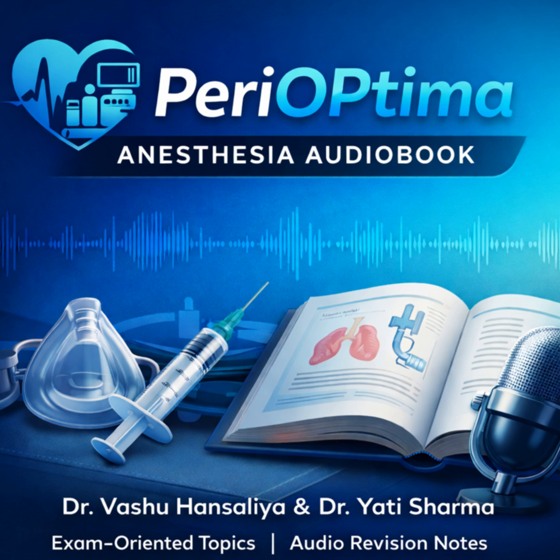So you check it first. High pressure, working Yankauer, ready to go. Okay. O is oxygen. Verify the pipeline pressure. But crucially, and this is a common mistake, verify the backup cylinder. Remote sites are notorious for pipeline failures or pressure drops. You need a full E-cylinder on the back of your machine, and you need to have checked it's full. Got it. A is airway.